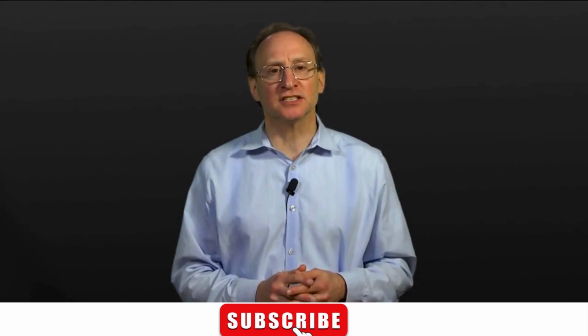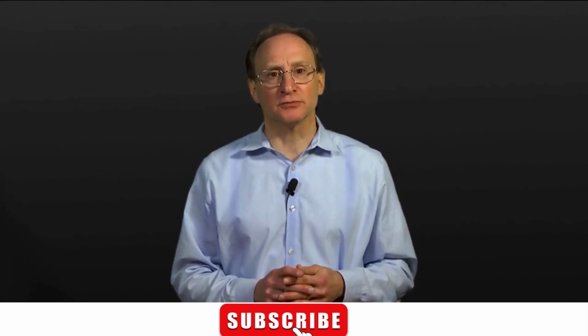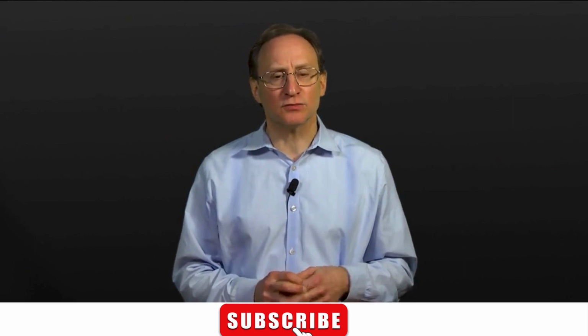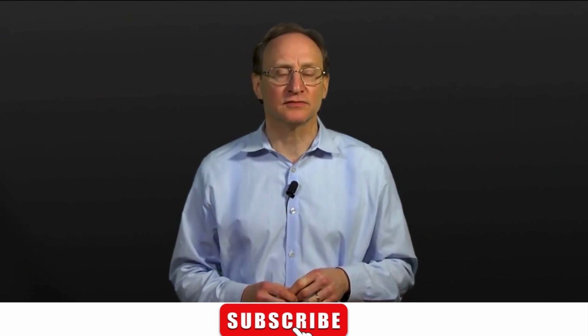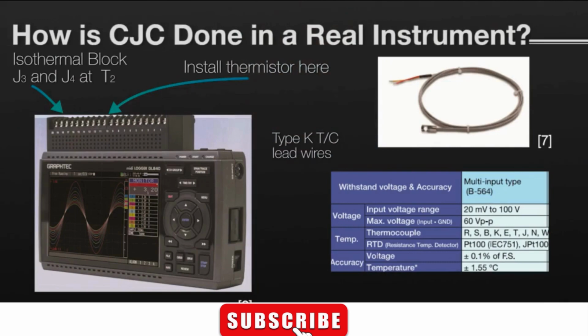Cold junction compensation is implemented in every process instrument with thermocouple input. Here's one real-world example of how this is done. The Graphtec GL840 data logger has a terminal block at the top. Users connect thermocouple wiring from external thermocouple probes to this block. The terminal block implements the isothermal terminal block shown in the previous slide. The temperature T2 of the block roughly corresponds to the ambient temperature where the data logger is located. But a thermistor inside that terminal block measures the exact block temperature.